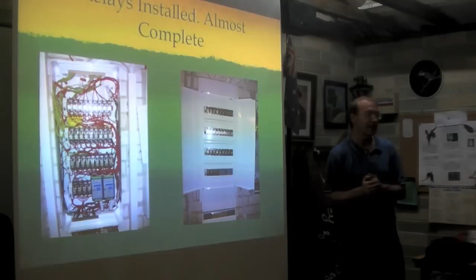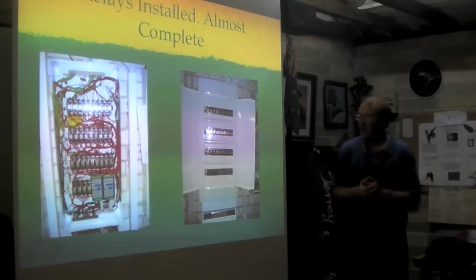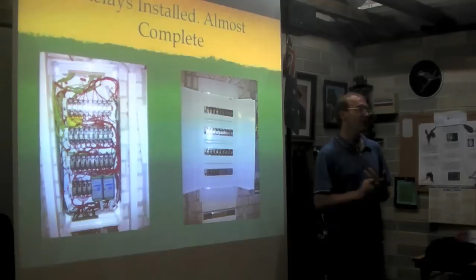Therefore, I could use 1mm copper wire, which meant I could reduce the cost of the install significantly. There's method in my madness, and there are actually 2 cabinets of relays. My light switches only have 12 volts on them now, but I used 240 volt rated cable for them. The reason is that I can retrofit and get rid of the control system if I want to, and I could run the 2 cables down the same conduit next to each other, because I used the cable rated for the highest rating.